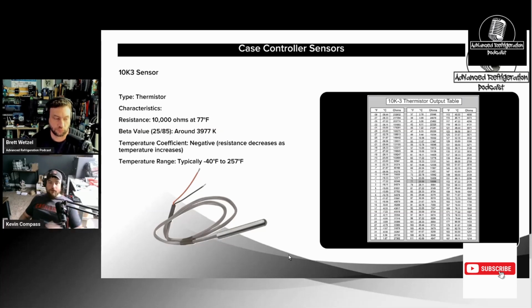At that point, you're going to resplice your connections, or recheck it and then try it again. You still could have a bad cable. Some mouse got it, bit it. This is all done with the sensor disconnected from the board, Molex plug pulled out, whatever. You also want to check from leg to leg and see if it's shorted, because you could have a mouse that chewed through and you got a strand, just shorting that thing out, or someone was tugging on it.